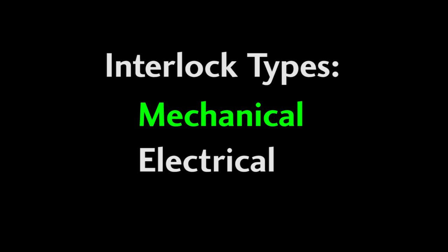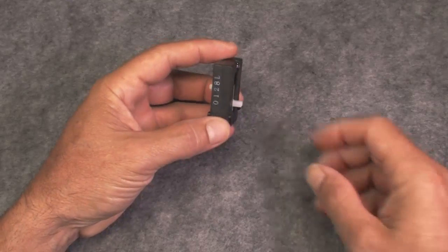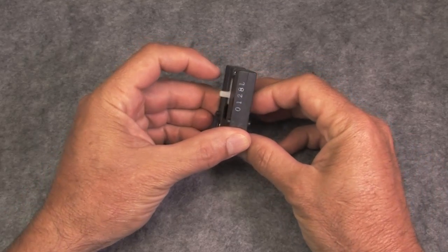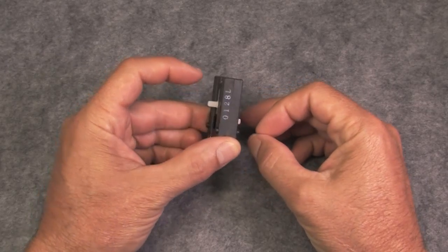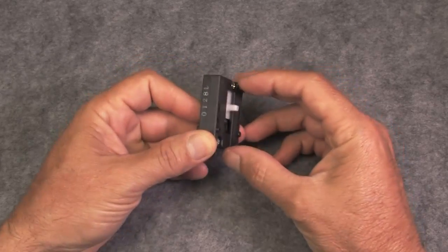The quickest and easiest way is to add a mechanical interlock like this Fuji module. When one contactor pulls down one side of this interlocking device, the other side gets locked up and can't be pulled down. When the other side is pulled down, the original side is locked up.